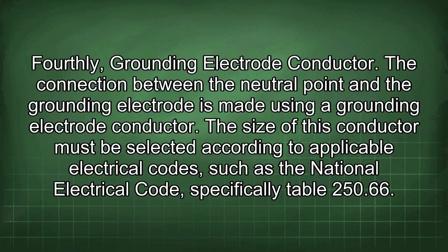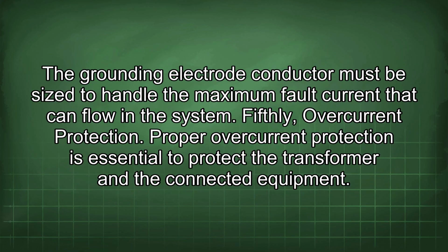Fourthly, grounding electrode conductor. The connection between the neutral point and the grounding electrode is made using a grounding electrode conductor. The size of this conductor must be selected according to applicable electrical codes, such as the National Electrical Code, specifically Table 250.66. The grounding electrode conductor must be sized to handle the maximum fault current that can flow in the system.